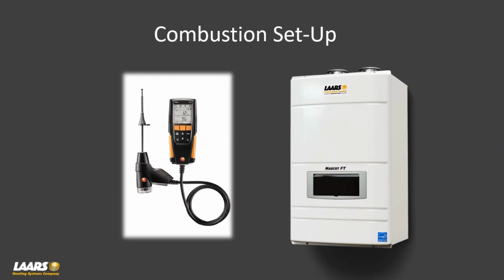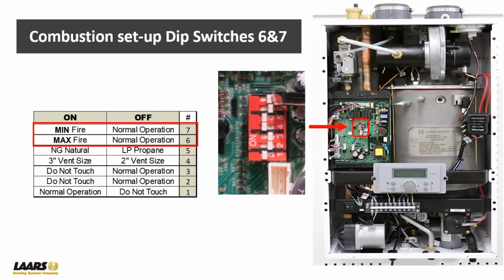Next, we'll talk about combustion setup. Every manufacturer on the market, over 84%, requires a combustion analysis. We see a lot of contractors that don't own analyzers. You really should. And especially if you're doing any type of preventive maintenance, it's great revenue for you. You can tell your customer you're going to come in annually, not only go through the equipment, but you do a combustion analysis and make sure it's running at peak performance. But you need a combustion analysis done. So we're going to talk about that next.